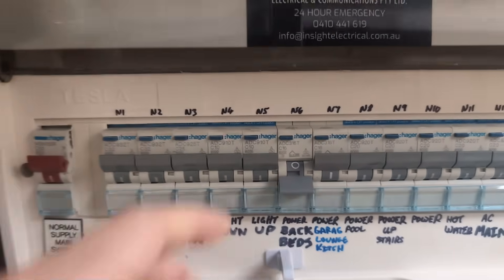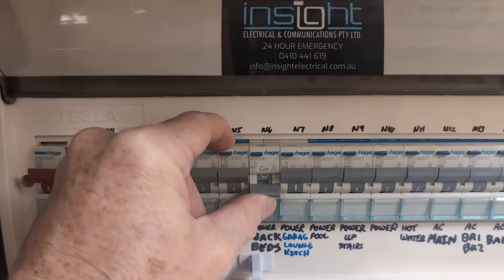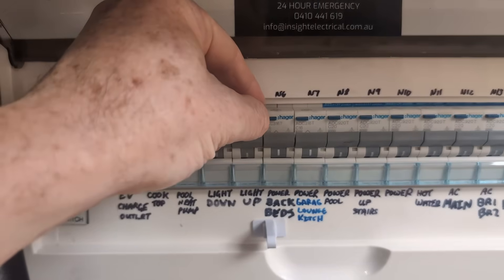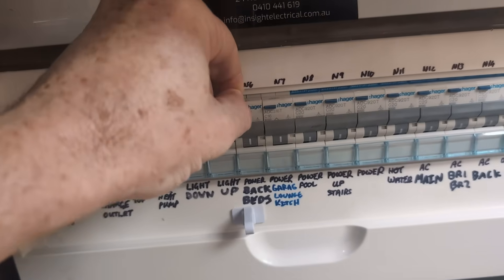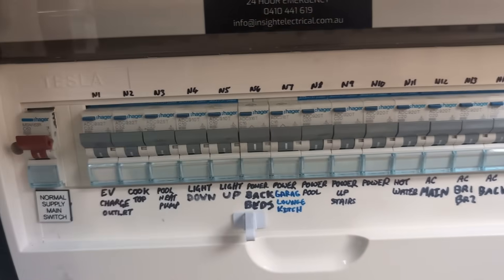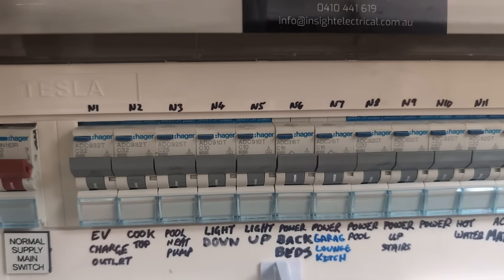So let's switch this back on. We've got minimal load on there at the moment — just the one clock. This was tripping before, just constantly tripping out. But look, it's got the earth leakage test button. I press that — but it doesn't work. If I test this other one here, it works just fine and dandy. But this one doesn't work. That is definitely faulty.